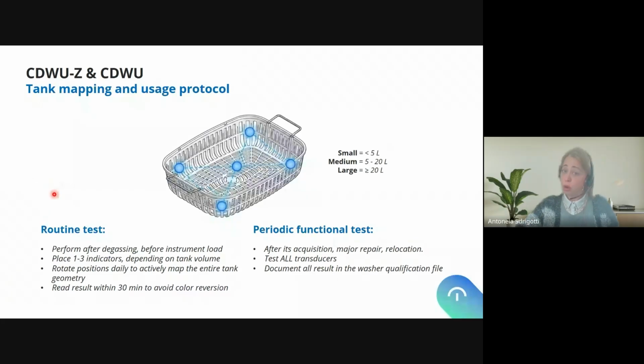So what is a routine test in the case of an ultrasonic washer? It is every time we change the solution. Fingers crossed, this should be at least once per day, because the more cycles we do, the more organic residues we will have in that solution. So the ideal would be one cycle, then change of solution. But if we don't do this, at least we should do this. Of course, it will depend on the level of organic residues or dirt on my instruments and how many cycles we perform, but the idea is to change the solution after every cycle.